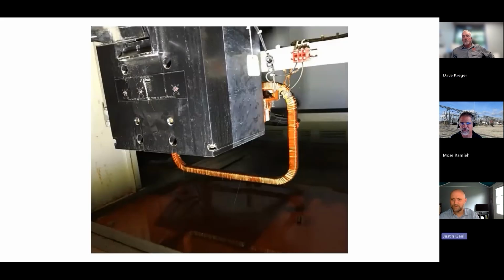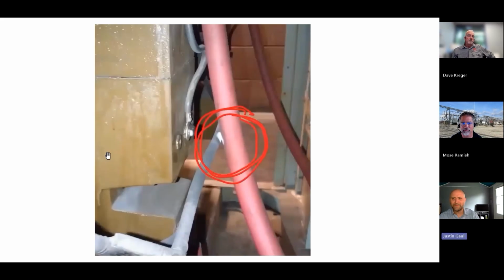So that's one example. Here's another thing that I think we commonly look for. There's a little corona action there. Yeah. So this happens once again more often than you think, right? We have red jumper cable, 15 kV unshielded jumper cable, and it does not like to be long term in proximity to a grounded plane, or worse yet, in proximity to another phase.